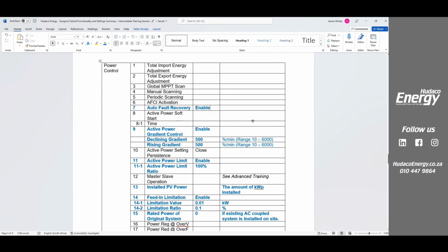So in other words, if there is a fault, the system will recover itself. Often, if there's a grid over voltage, if there's a comms error from the BMS, if there's a power outage, something like that, then the system will recover by itself. If you disable that, whenever there's a system error, the system will wait for you to come and have a look, say what's going on here. It's really for safety, just to say, do we want to do it? And in fact, most of the time for a residential system, we wouldn't have it. Where guys would really use auto fault recovery off is on a big utility scale plant, you know, if there's a, I don't know, earthing issue.